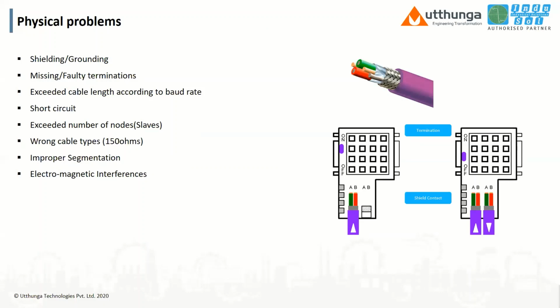What are the physical problems we are facing at the maintenance level? Shielding is not perfect, or faulty terminations. Terminations are not as per standard, or cable length is exceeded according to the standard. As we mentioned, for 1.5 Mbps the standard is 200 meters. If we exceed 200 meters, what will happen? Communication will get interrupted. Short circuit in the A and B connections will also interrupt the communication.